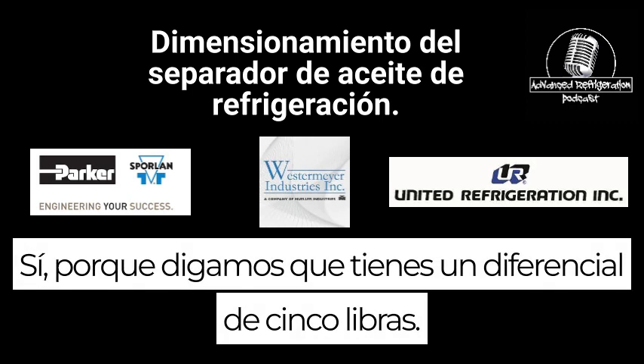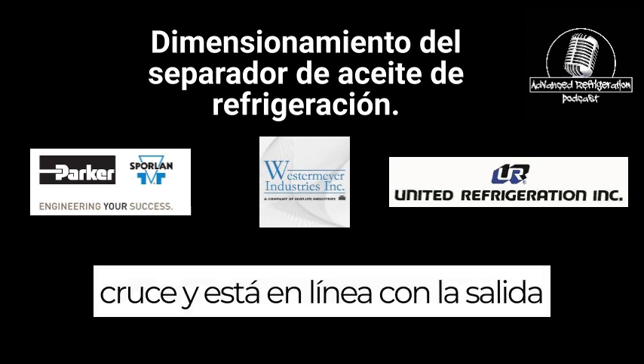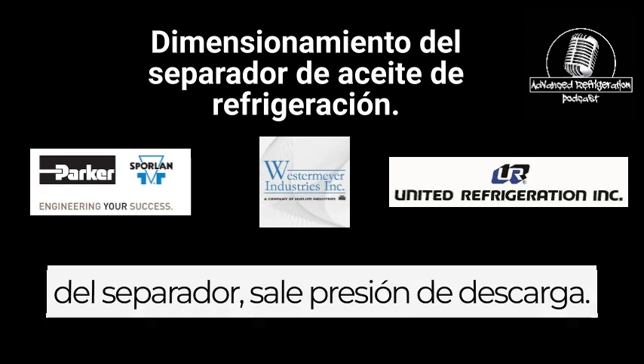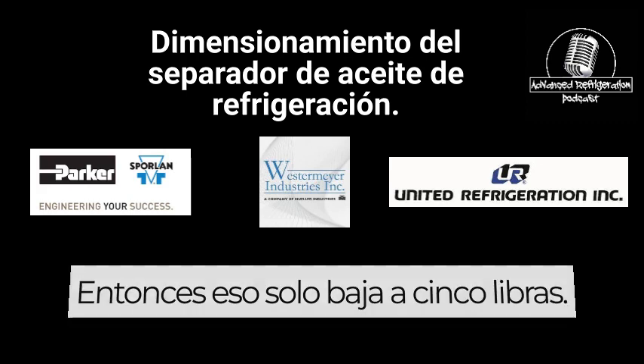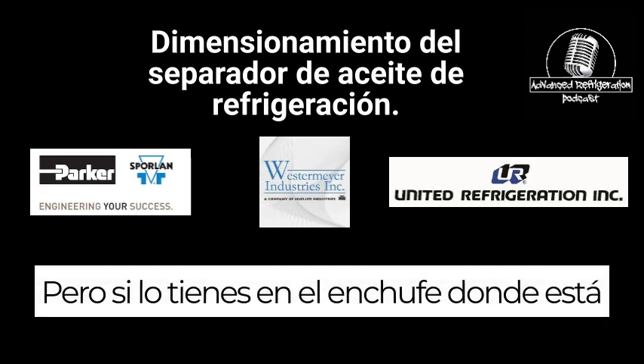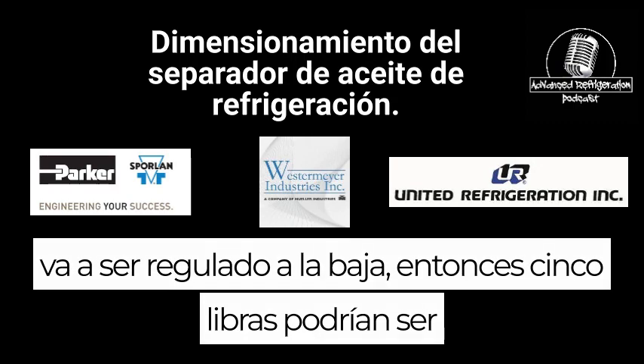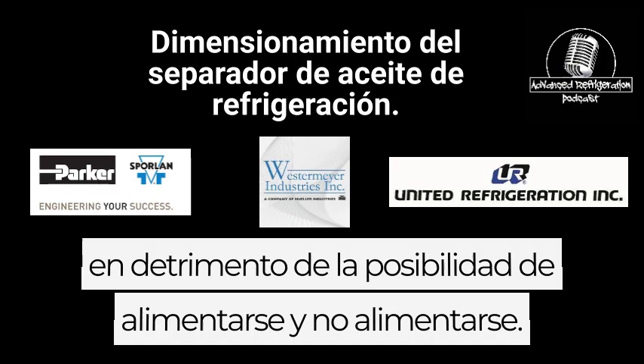Yeah, because let's say you have a 5-pound differential across it, and it's in line coming out of the separator. You've got discharge pressure coming out, so it only drops 5 pounds. But if you have it on the outlet, where it's going to be regulated down, then 5 pounds could be detrimental to the possibility of feeding and not feeding. Correct.